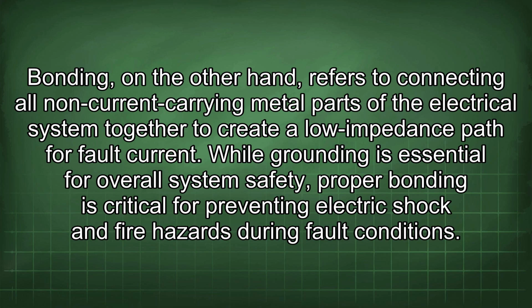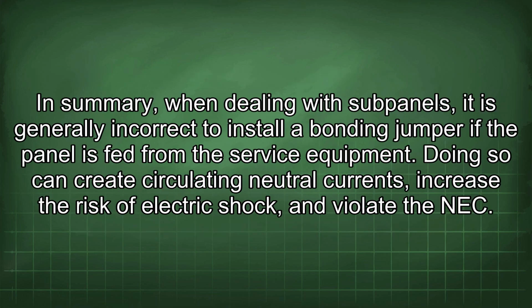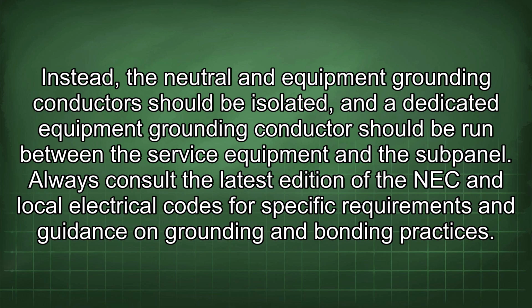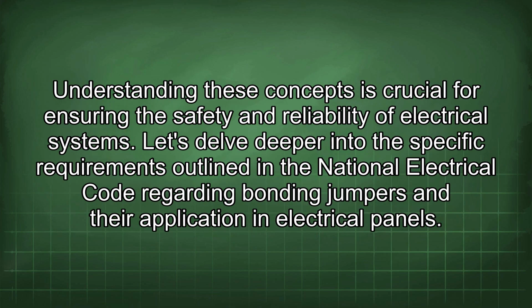fault conditions. In summary, when dealing with subpanels, it is generally incorrect to install a bonding jumper if the panel is fed from the service equipment. Doing so can create circulating neutral currents, increase the risk of electric shock, and violate the NEC. Instead, the neutral and equipment grounding conductors should be isolated, and a dedicated equipment grounding conductor should be run between the service equipment and the subpanel. Always consult the latest edition of the NEC and local electrical codes for specific requirements and guidance on grounding and bonding practices. Understanding these concepts is crucial for ensuring the safety and reliability of electrical systems.